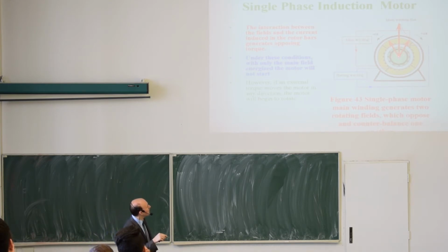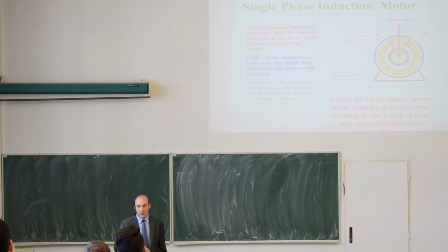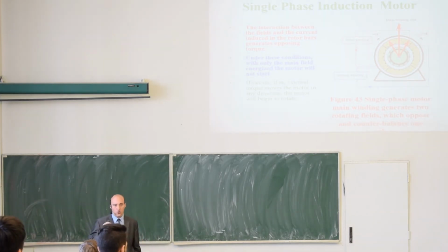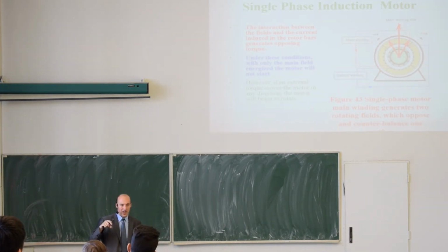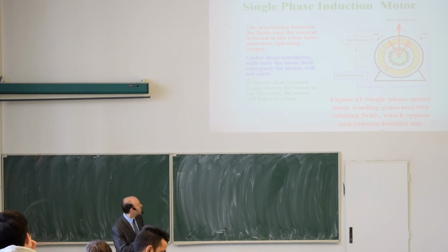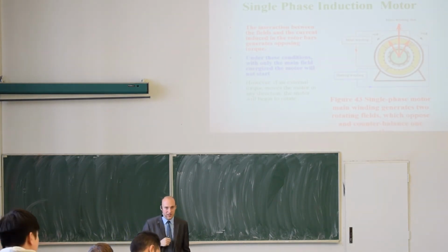You can see it here. So we can imagine that this is one magnetic flux from one, let's say, virtual rotating magnetic field, and this is the opposite direction. If they sum, I will have this direction and a different size, but without the auxiliary winding, it will still be in a single direction. So we can connect the auxiliary winding to a circuit that will provide us a different voltage with a different phase. So either we could have a two-phase power network which we don't, but we could create that. And we could power this starting winding with the second phase in our system.